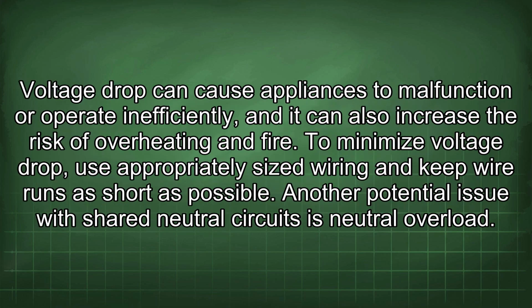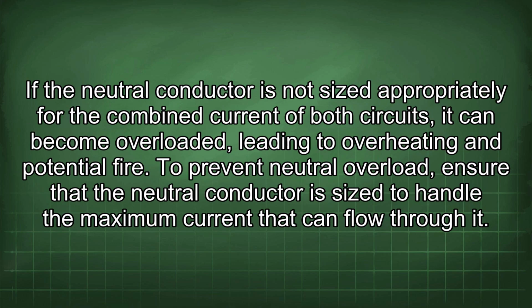Voltage drop can cause appliances to malfunction or operate inefficiently, and it can also increase the risk of overheating and fire. To minimize voltage drop, use appropriately sized wiring and keep wire runs as short as possible. Another potential issue with shared neutral circuits is neutral overload. If the neutral conductor is not sized appropriately for the combined current of both circuits, it can become overloaded, leading to overheating and potential fire.